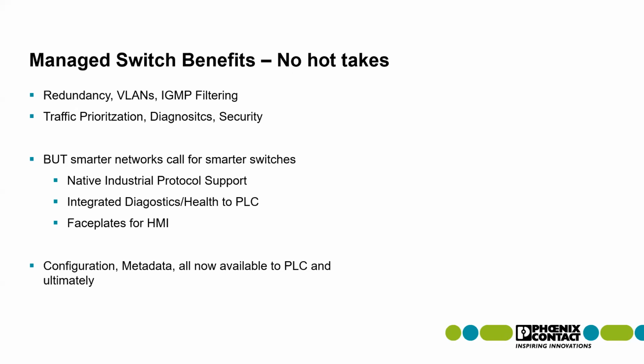You can actually plan for different things happening within your infrastructure. The switch can report that information to your control platform, and now it's your PLC that's making intelligent decisions about if it wants to do something different in its application, whether that's shutting down a port, or doing something programmatically like speeding up the line or slowing down the line. Maybe you're seeing your port utilization creep higher and higher to 90%. Rather than have dropped packets, maybe it makes more sense to slow down your production line or to spin down a line to allow that network to remain in a healthy state.